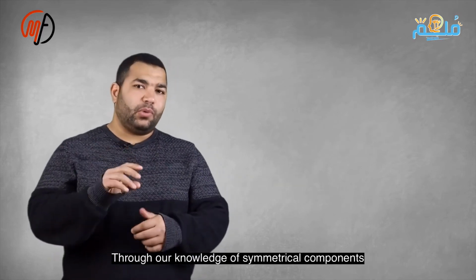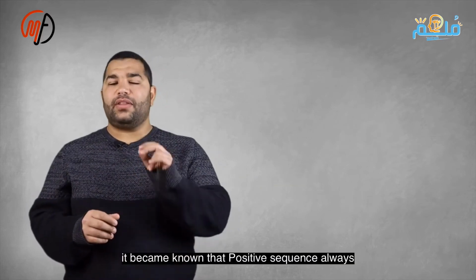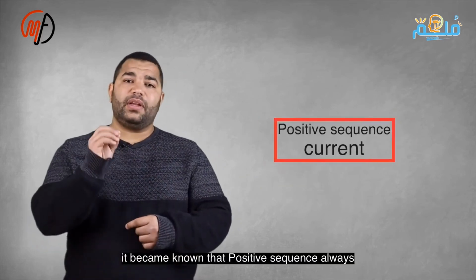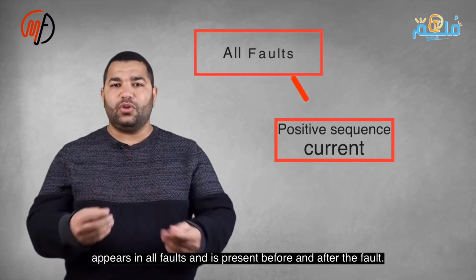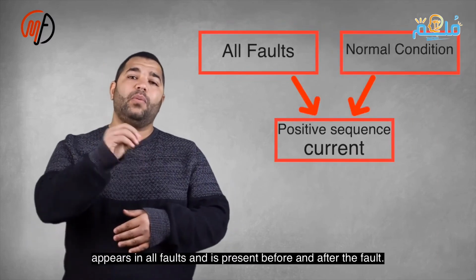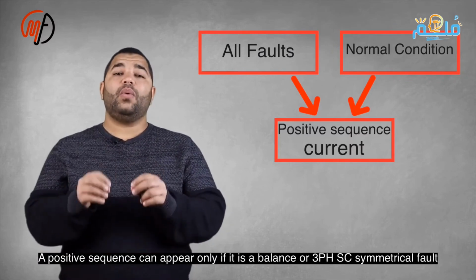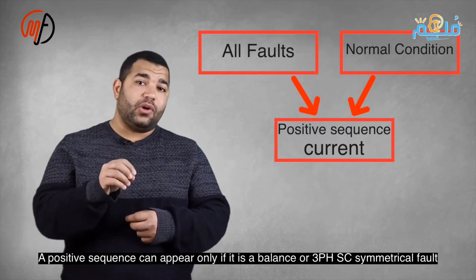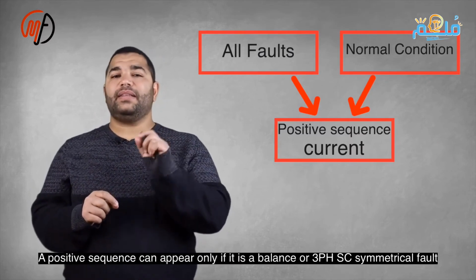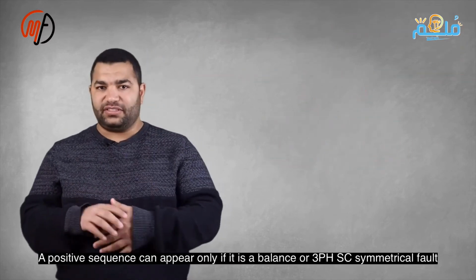Understanding the symmetrical components reveals that the positive sequence is always present in all faults. It appears alone in balanced faults. The negative sequence appears in unbalanced systems or faults. The zero sequence appears if the ground is involved in the fault. In symmetrical faults, no zero sequence is present. Thus, in a symmetrical fault, only the positive sequence appears.